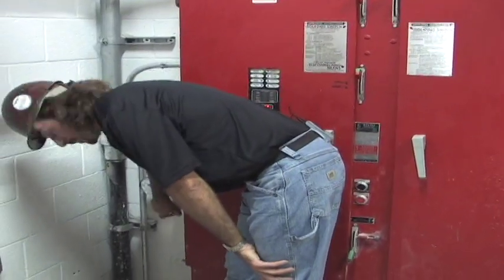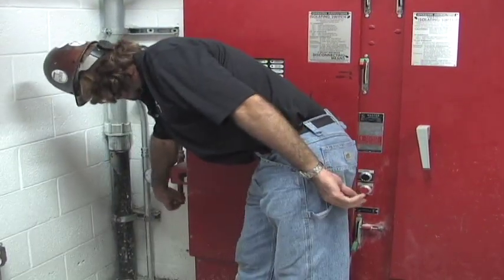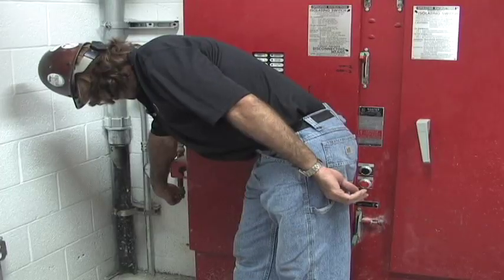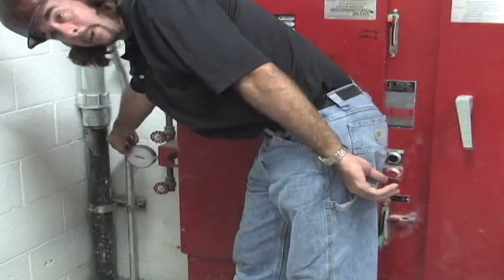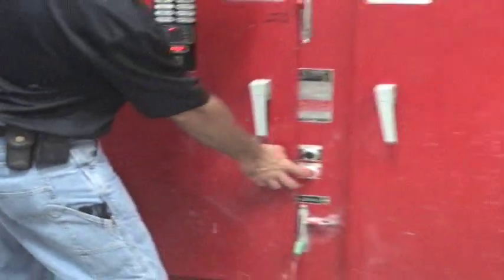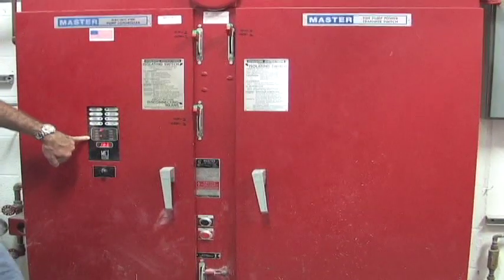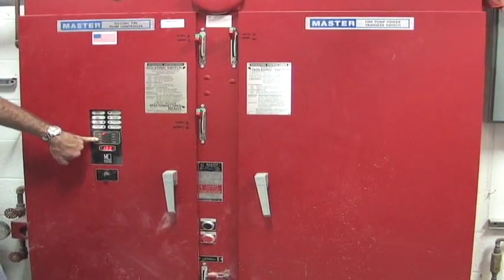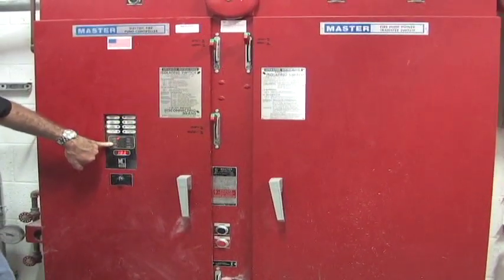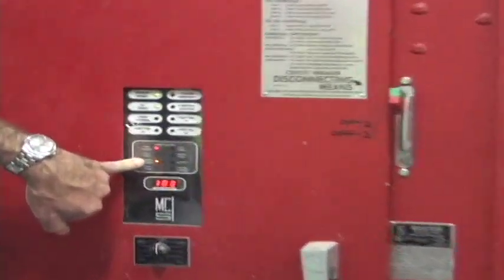Crack open the valve just the same way we did the Jockey pump. We've got our black mark here at 150 psi. Once we get to that 150 psi, our fire pump's going to kick on. As you can see, our timer is blinking right here. This is going to blink for 10 minutes, and after 10 minutes, the fire pump's going to shut off.